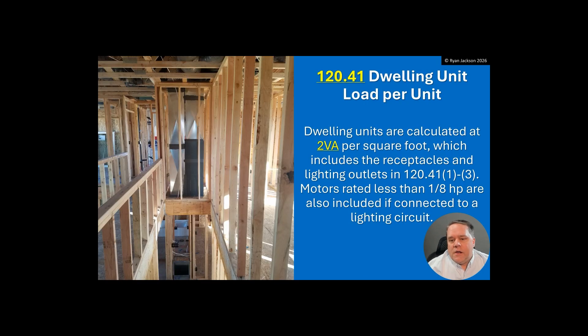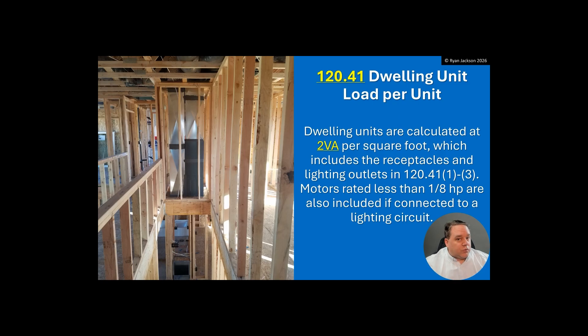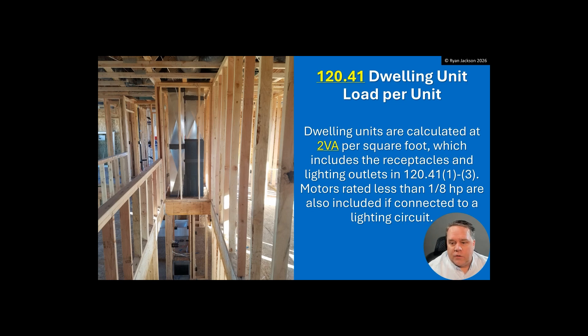Dwelling units are now calculated at two volt-amps per square foot — it's been three VA for decades, probably 50 to 70 years. That two VA per square foot includes your receptacles and your lighting outlets under 120.41 items one through three. Motors rated less than one-eighth horsepower are also included if connected to a lighting circuit.